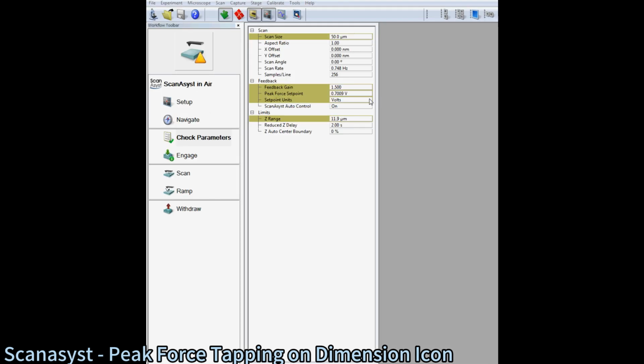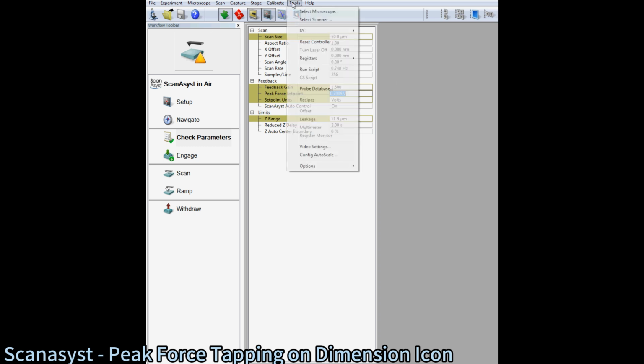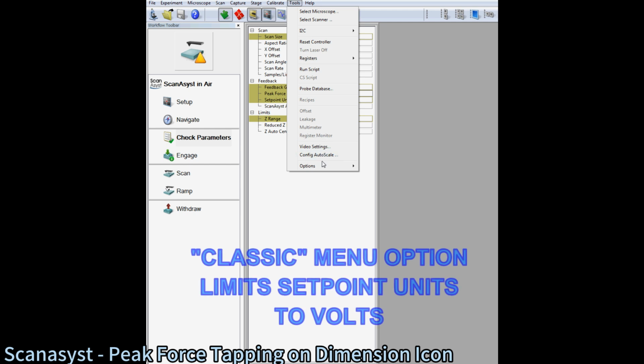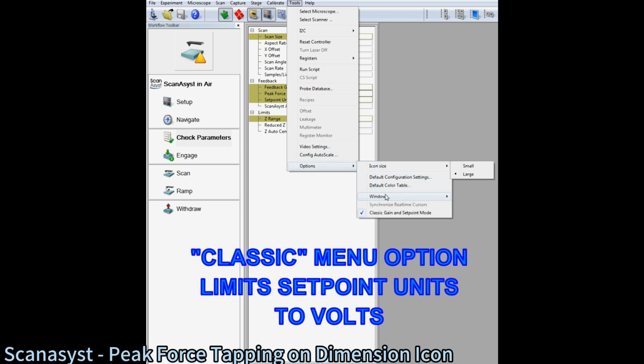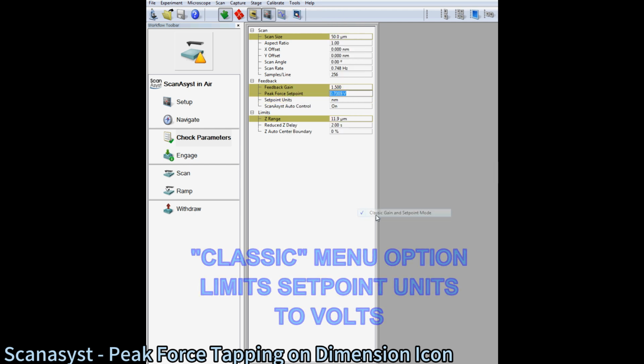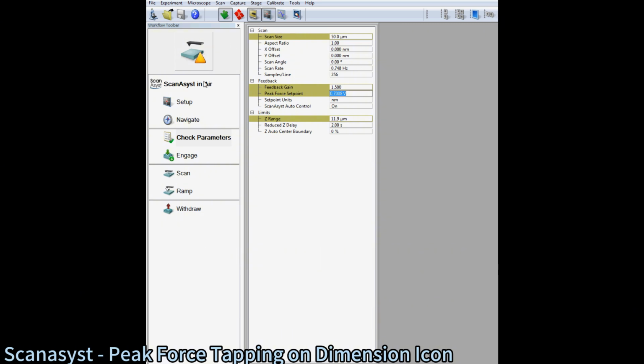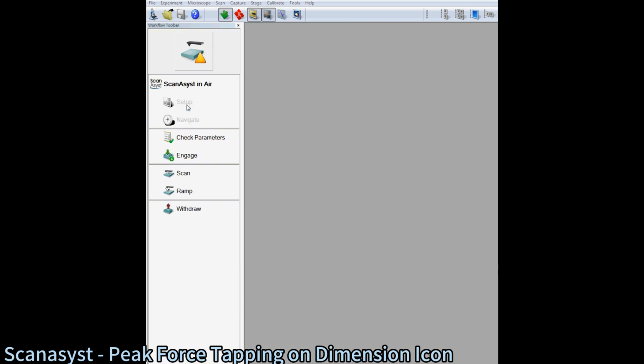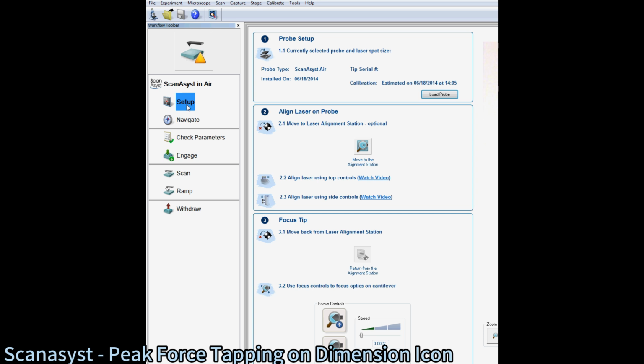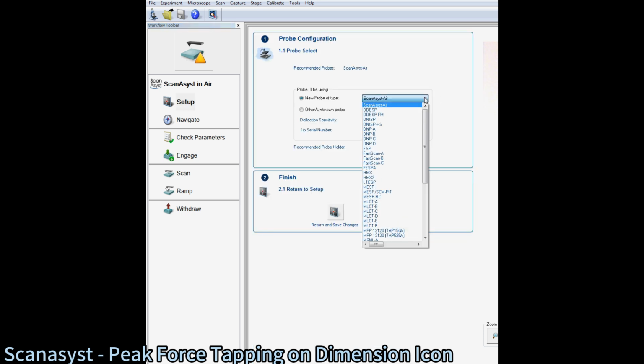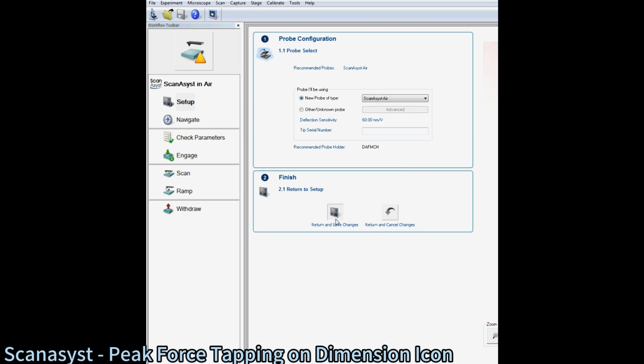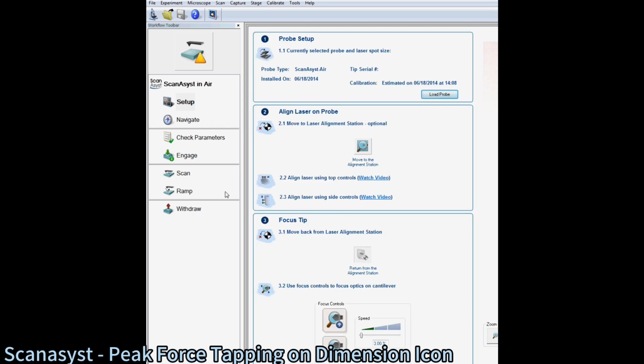If your software configuration is displaying the set point value in volts and you prefer to use force units, then open the Tools pull-down menu and select Options. The pop-up side menu displays an option labeled Classic Gain and Set Point Mode. If this option is checked, click on it to deselect the option and then open the Setup interface again and select the ScanAsyst probe once more. Afterwards, open the Parameters interface and the set point should display in force units.